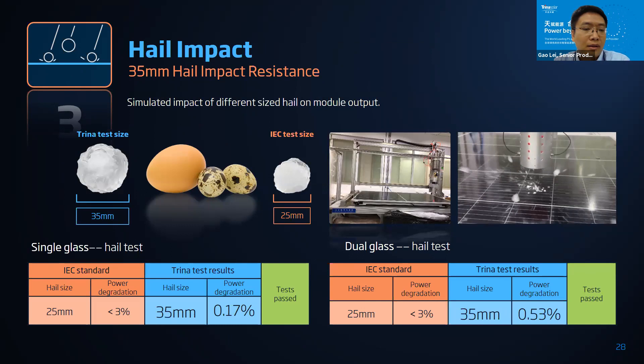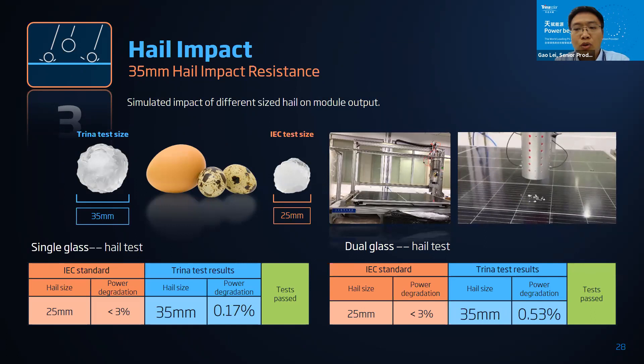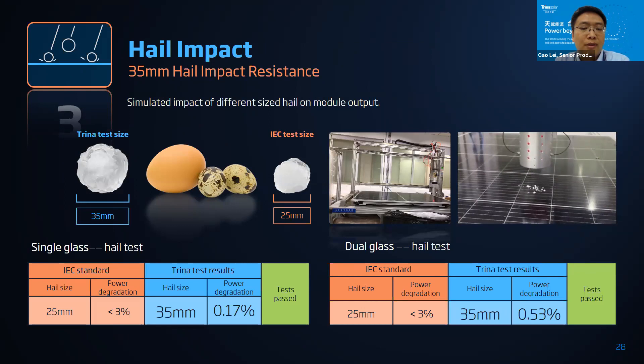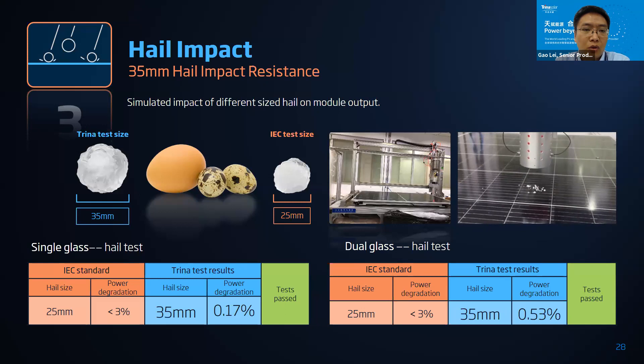Enhanced test number three is a hail impact simulation. We conducted two tests: one is the standard IEC test and another is a test with 35mm hailstones. After the tests we measured module degradation. For single glass the degradation is 0.17 percent, and for dual glass it is less than 1 percent — specifically 0.53 percent. If you need a more strict hail impact solution, please contact Trina Solar — we have a solution for you.